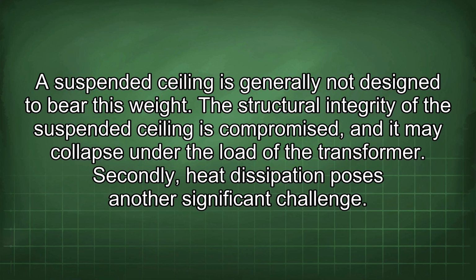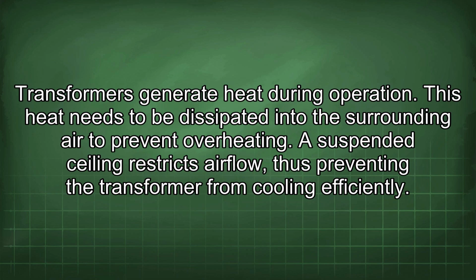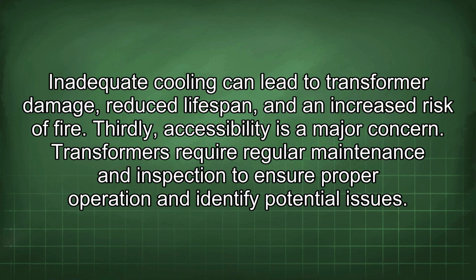Secondly, heat dissipation poses another significant challenge. Transformers generate heat during operation. This heat needs to be dissipated into the surrounding air to prevent overheating. A suspended ceiling restricts airflow, thus preventing the transformer from cooling efficiently. Inadequate cooling can lead to transformer damage, reduced lifespan, and an increased risk of fire.